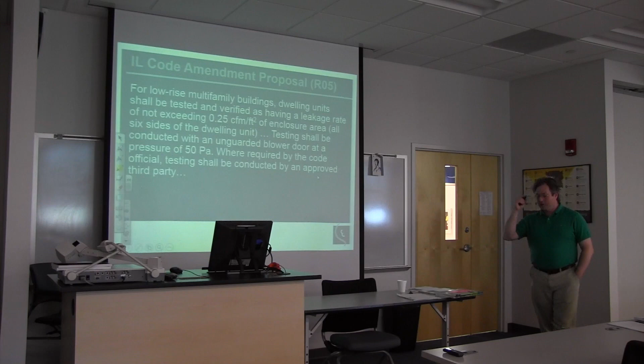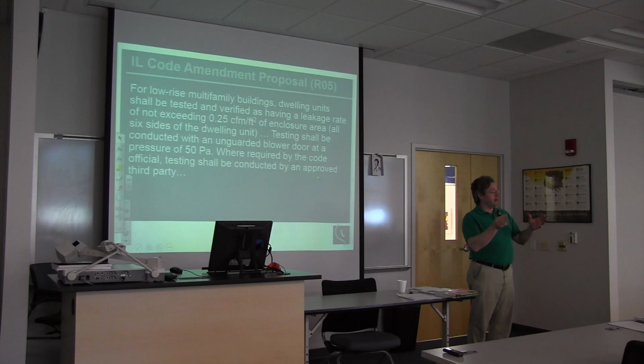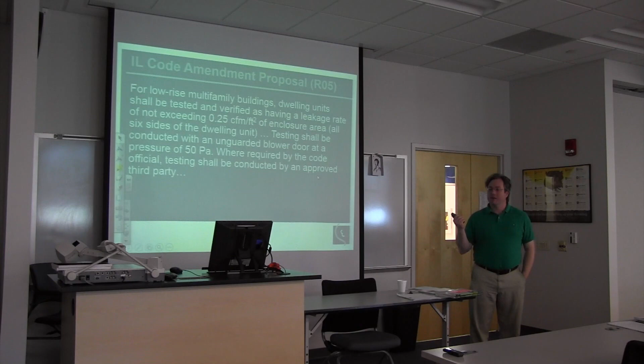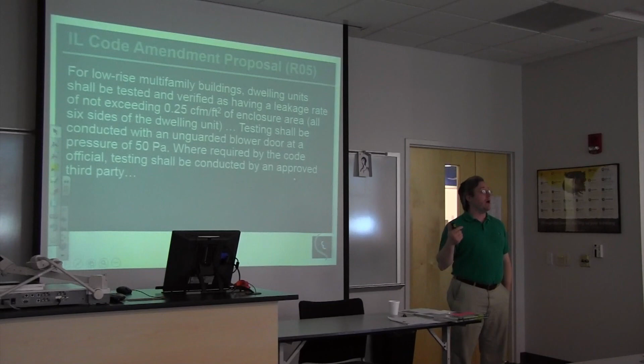High-efficiency lighting, again similar to commercial. Going back to the residential multifamily, multi-unit question, there's a proposed amendment to allow for individual blower door testing and sampling. Because when you end up with high surface area to volume ratios, your ACH really becomes problematic - a little bit of leak across the whole surface area can really screw up your ACH on smaller test areas. So this allows you to do an air leakage test based on surface area rather than ACH, similar to what's allowed in commercial, but bringing it over to residential.